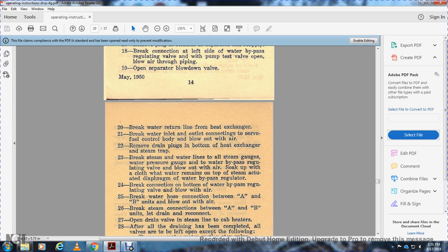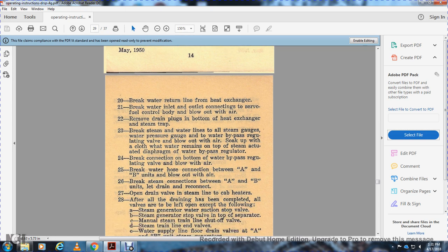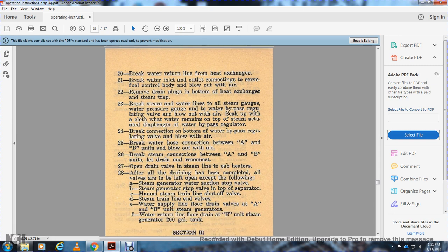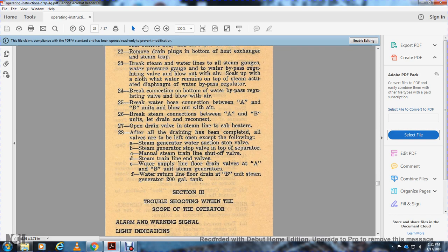26, break the steam connection with the A and B units to let the drain reconnect. 27, open the drain valve in the steam line to cab heaters. 28, after all the draining has been completed, all the valves are left open except for the following: steam generator water suction stop valve; steam generator stop valve at the top of the separator; C, the manual steam train line valve, the shutoff valve; D, the steam train line valve; and E, the water supply line with the floor drain valve, the A and B unit steam generators; F, the water return line, floor drain valve, B unit steam generator, 200-gallon tank.